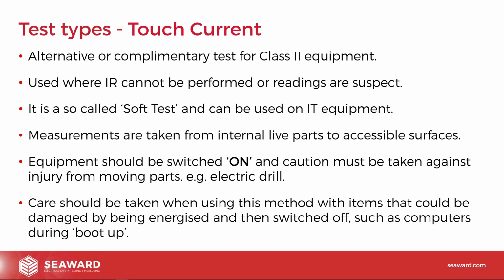We are powering the equipment up, we're running the equipment, so we've got to be very careful when we're carrying out this test, because the equipment is running up, it is getting hotter, it is actually spinning around or whatever. So again, we've got to be careful on the safety precautions, the PPE and all that sort of thing that we might need to use when we're doing it. But it is a very accurate test. It will tell you, is that part safe? Does that part have any dangerous touch currents on it? So again, a very useful test, but it needs to be done and understood as part of the mixture of other tests, and maybe done alongside something like insulation resistance first before you carry out these tests.